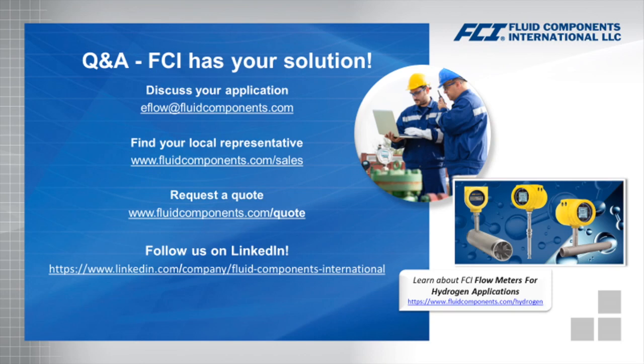All right, next one here, and I apologize if some of these are similar to each other. For small bore pipe work, a 1-inch line, is it better going up a line size to get a better Reynolds number for accuracy? That one, again, you've got to talk to your manufacturers because, yes, if you go up in line size, it will change where your Reynolds number is impacted.